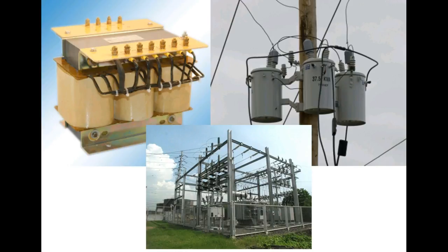But we transmit them over here. This over here might be 75,000 volts. Over here, this might be 2,300 volts. I send the 2,300 volts out on power lines, and then my house has a transformer out there, which steps it down to 240 or 120 for my use, right? You understand? The only function of those substations is to take that high voltage and step it down to a lower voltage for safety. It's not really low. It's still pretty high.